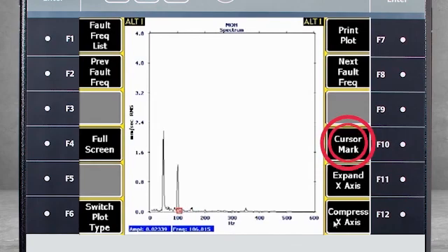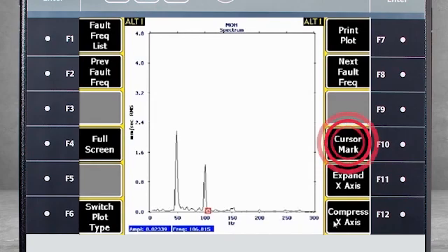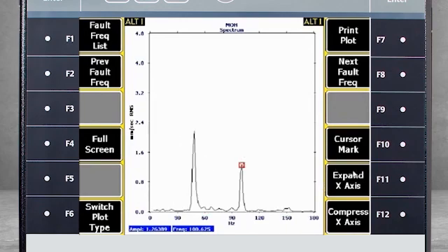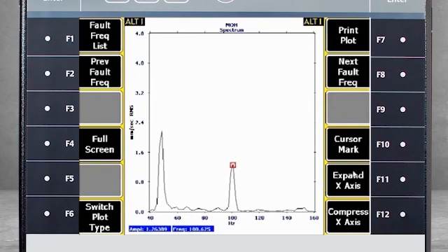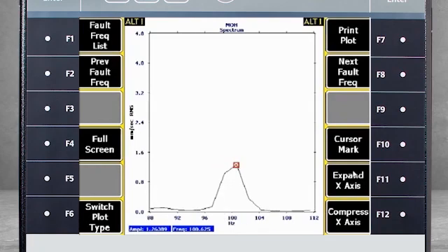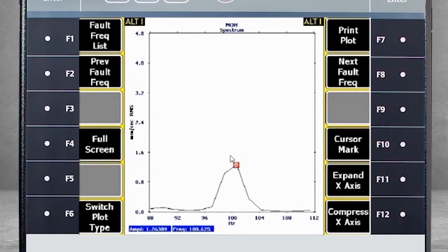Now let's talk about F10, the cursor mark. First we start by placing a cursor on top of a peak. Now when you expand or zoom in on the data, you are doing so in a certain moment in time. With multiple expansions, you will see the resolution lines. If you see the digital resolution lines, you can imagine that the peak is not actually here under the cursor. If this scenario were analog, the real peak would be here.